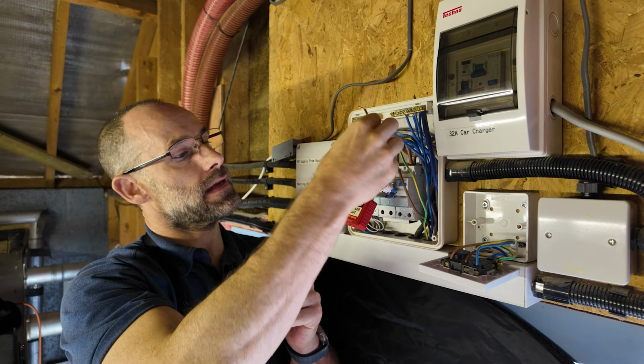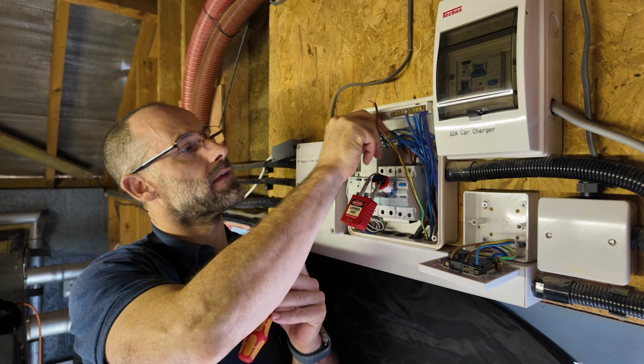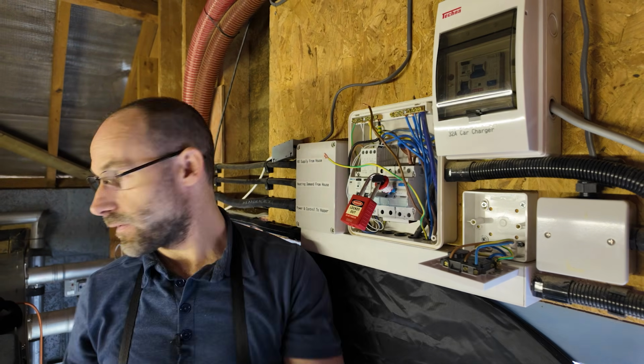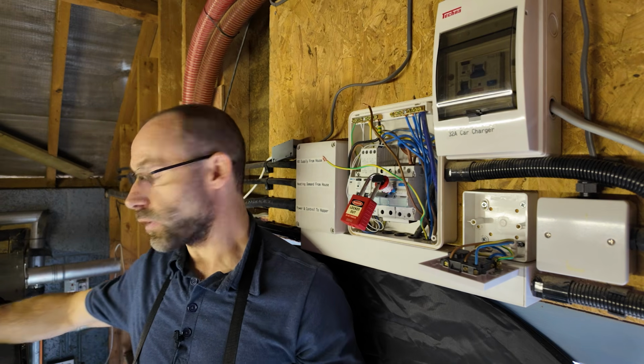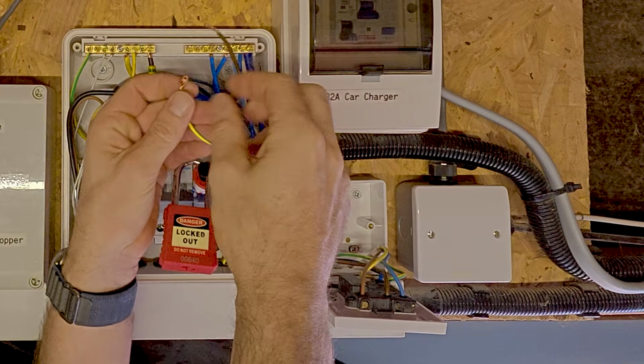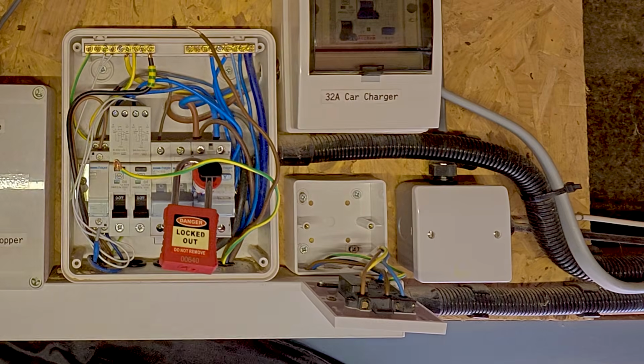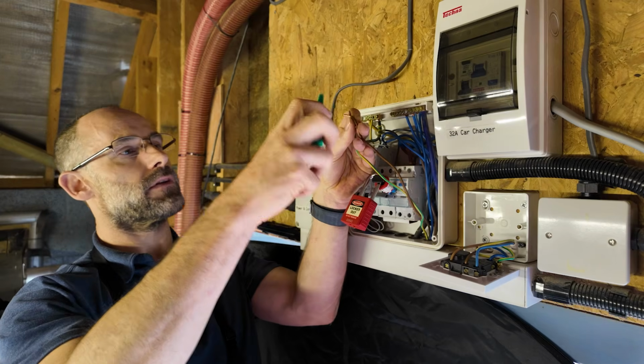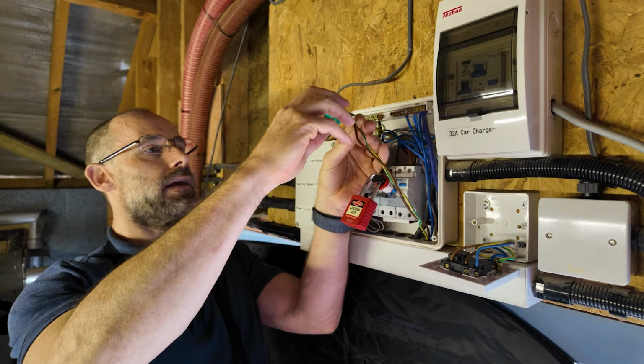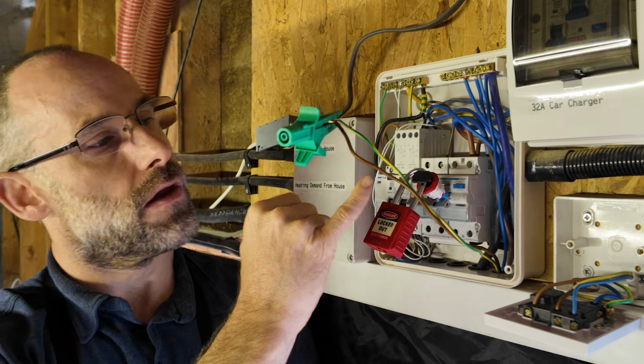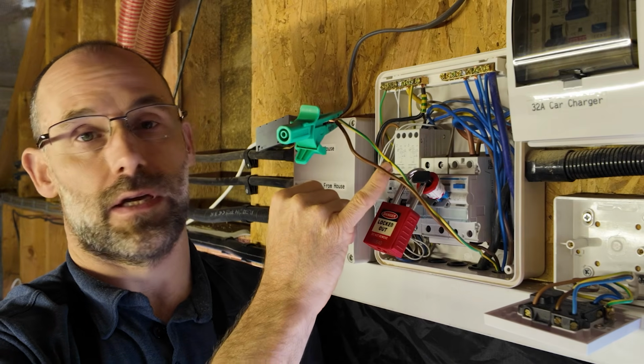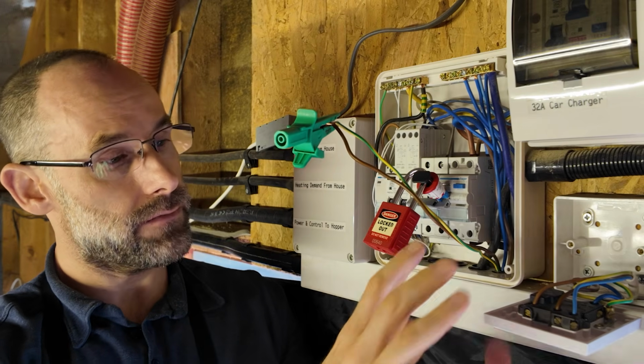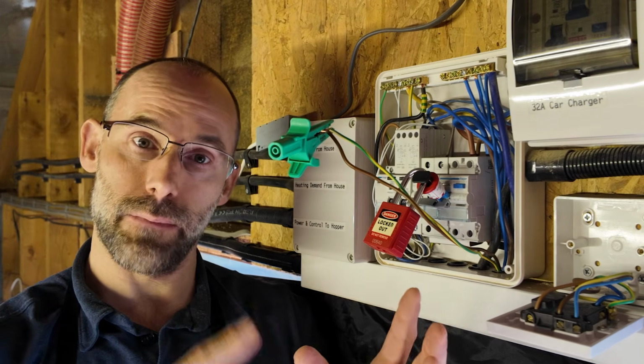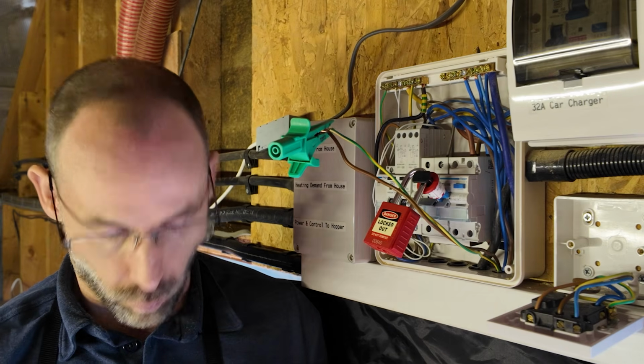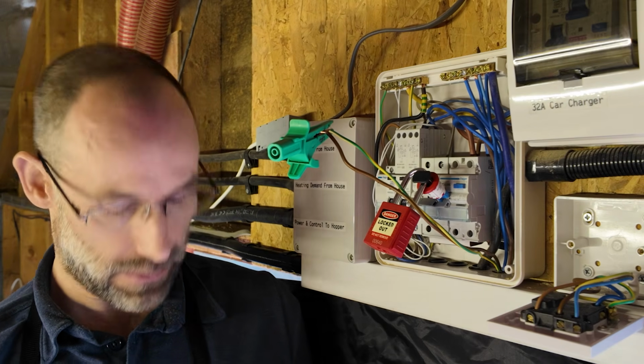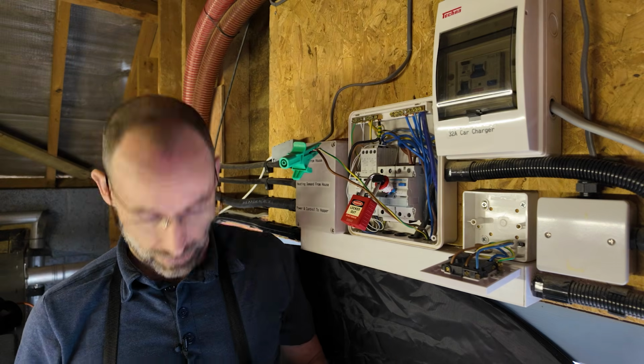So we can either plug the line straight into the earth terminal. I always find that's a bit weird. It's fine to do it, but if there was some strange wiring somewhere else, you could get yourself in trouble. So what I'm going to do is I'm just going to connect these two together. There's lots of ways to do that. One way would just be to use some testing clips. All right, so what I've done there is I've connected the line conductor with the circuit protective conductor. Now that means that even if this was a long, long way away, I can create a complete loop of wire using existing wires that are already here, which is really convenient. And now I can use that to do my continuity test.